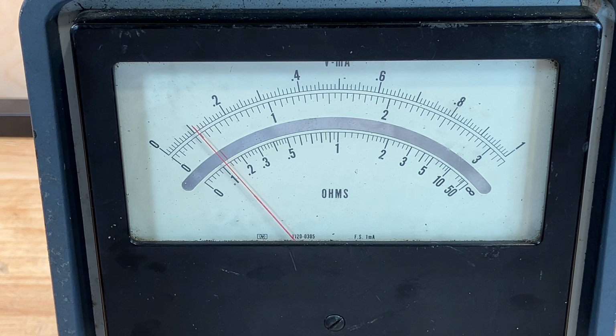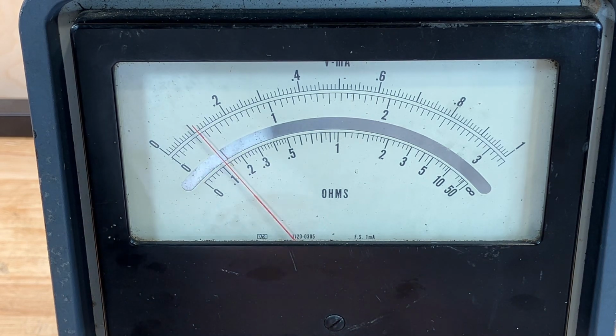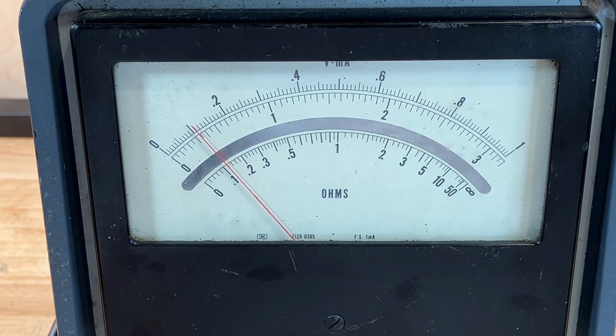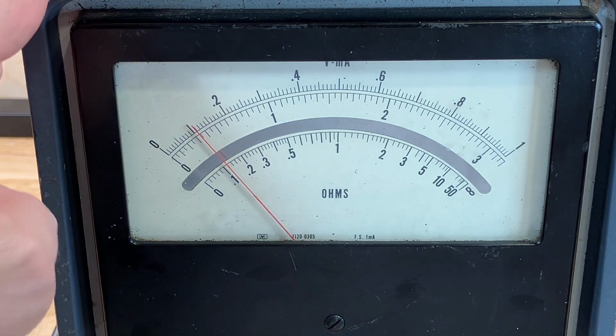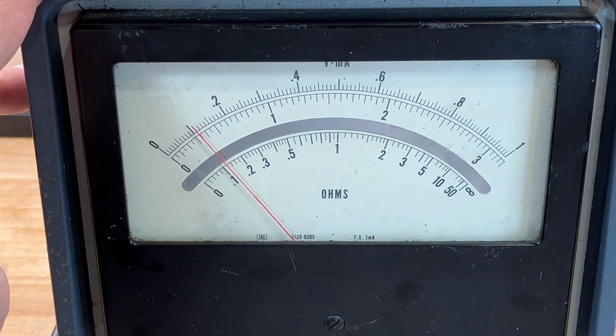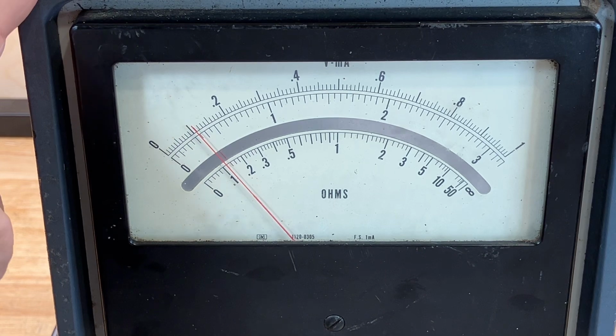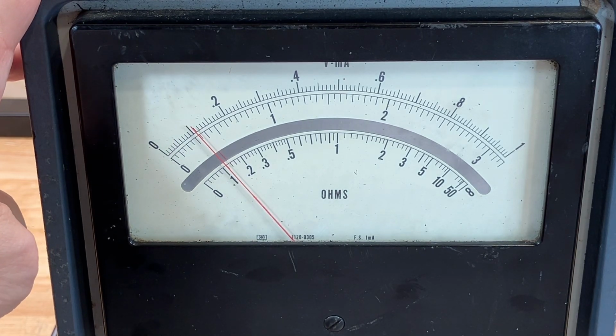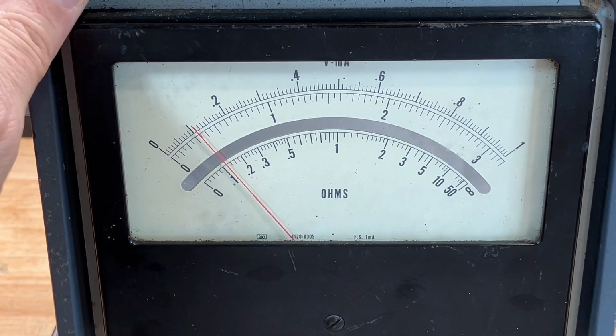It's really very dirty inside, so I thought I'd clean all the dust and dirt out, and clean all the switch contacts for every range. I also haven't gotten the power indicator light on the front panel to work, so I'm going to work on that. I'll probably end up replacing the line cord and getting the probes as cleaned up as I possibly can. I also have a replacement leather handle for the top - actually it's the whole rear case with an original leather handle still attached, that I bought as an extra for this instrument.